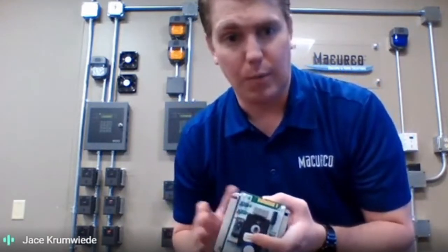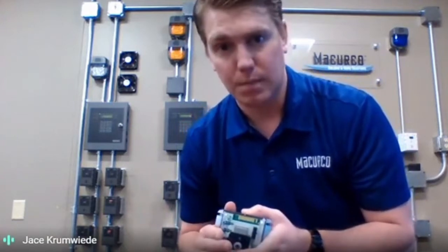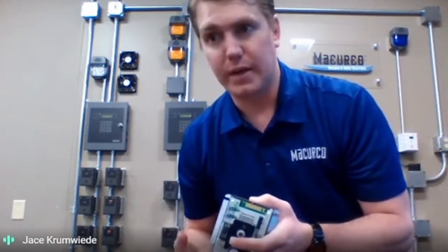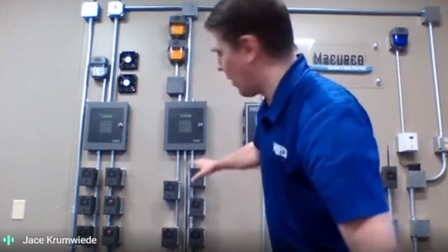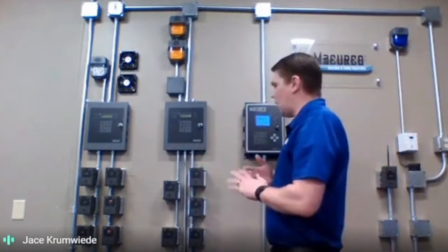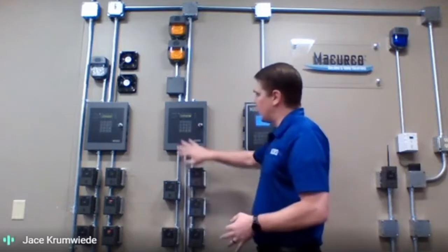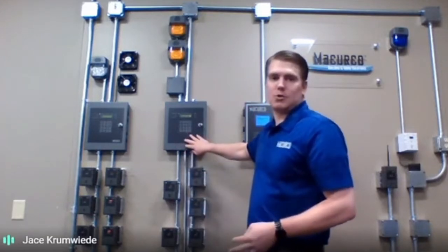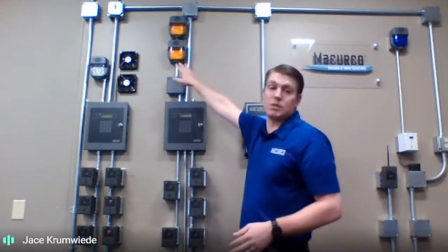One other aspect or output of what this unit does is it outputs a 4 to 20 milliamp analog signal. These can be used to run VFDs, variable frequency drives. They also are what are used to communicate to our control panels. So for larger installations, parking garages, ambulance bays, fire truck bays, things like that, where you're worried about carbon monoxide and nitrogen dioxide, all of these units can communicate back to a control panel, and that control panel is basically doing the outputs, doing the controls that you're looking for in a system.